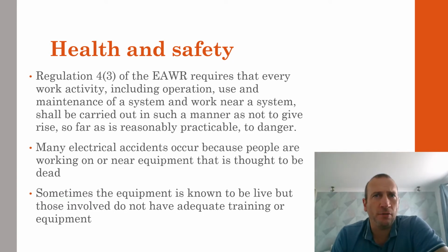The majority of electrical accidents happen when people working with electrical systems believe the supply is dead when it is not. There are times when a system is known to be live, but the duty holder does not have adequate training, equipment, or may even be neglecting certain responsibilities. The term reasonably practicable is not a get-out clause, as some would insist. The term is only used as there are rare situations where it may be required to work with live equipment. If this is the case, every reasonable precaution should be put in place and should be highlighted in a risk assessment.